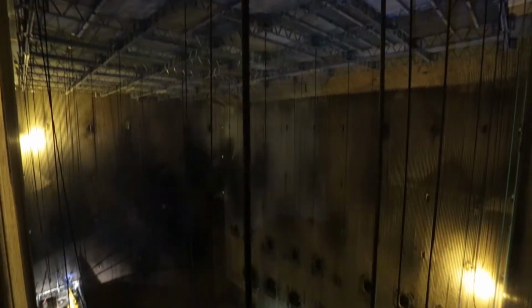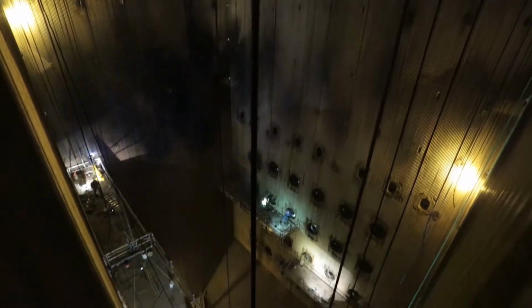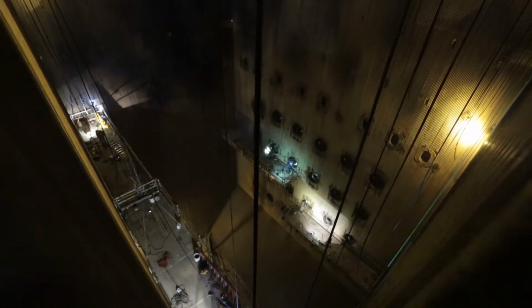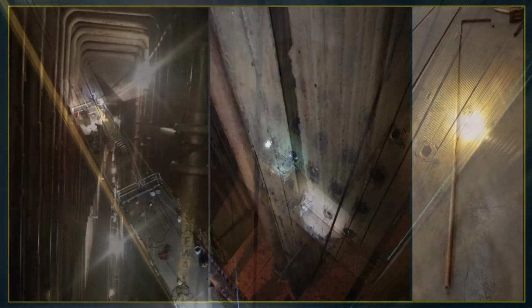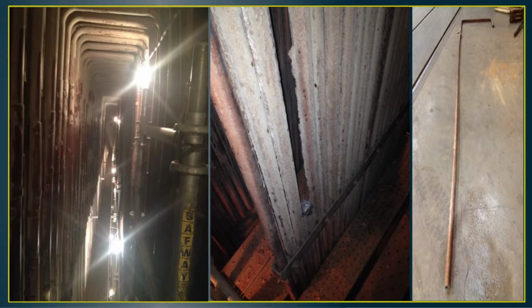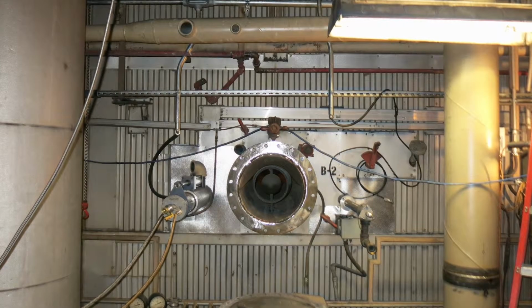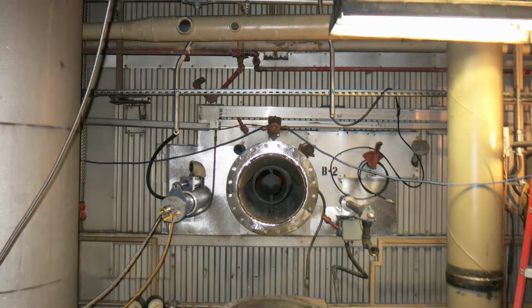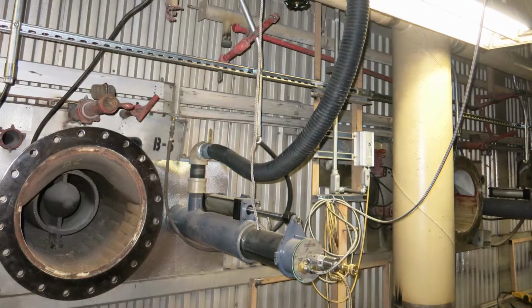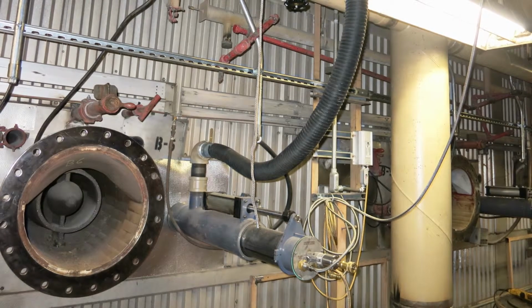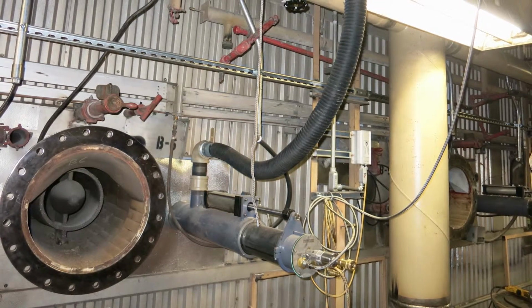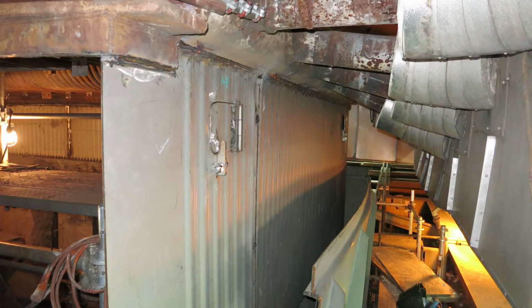Boiler quick deck was installed for inspections and repairs in the pendant area, and sky climbers were used for the burners and water wall tubes. Reheat pendant area was found with 9 improper material tubes that were cut out, and the proper material was bent and welded back in. Fuel oil igniters to meet the EPA MATS rule requirements were installed. These igniters require more airflow, and significant upgrade work has been accomplished to meet these requirements. Boiler seal trough skirting and screens to protect the seal trough header have been replaced.